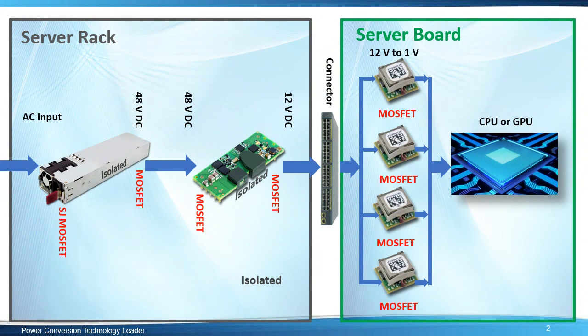First, let's look at the traditional server architecture, shown here, which uses rack-based 48-volt isolated and regulated DC-to-DC converters that convert to 12 volts, then the 12-volt to point-of-load converter to the CPU or GPU. Due to increasing power, many server designs — especially those adopted by new hyperscale servers and the latest generation of GPU-based AI servers — are migrating from 12-volt input to 48-volt input on the server board.